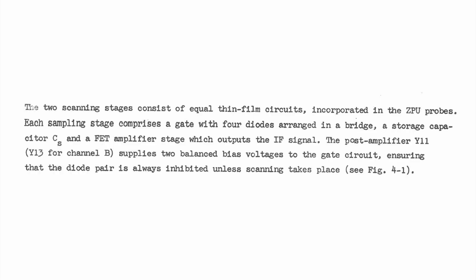A bit of information I found there is that the two scanning stages consist of equal thin film circuits incorporated in the ZPU probes, each of them comprised of a gate of 4 diodes arranged in a bridge, a storage capacitor and a FET amplifier stage. And then it goes to a post amplifier and some other things are happening there. But this is basically the part where the signal is being captured, brought to a 20 kilohertz signal, and then it's much easier basically to deal with, and we're going to do all the measurements that the device supports here.